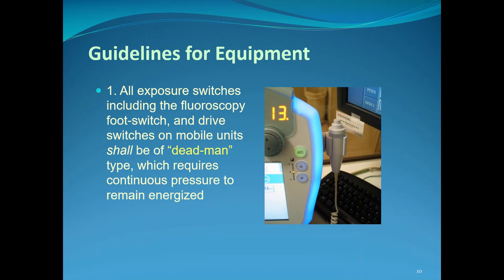Some equipment guidelines: exposure switches, including fluoroscopy foot switches and drive switches on mobile units, shall be of the dead man's type. This term comes from train conductor terminology — if a conductor were to die while driving, they would fall away from the throttle control and the train would stop. For us, the dead man's switch requires that if we set an exposure time of half a second, we must depress the switch and keep it depressed for at least that duration. If you let up on the button before the timer has gone off, the exposure will stop.